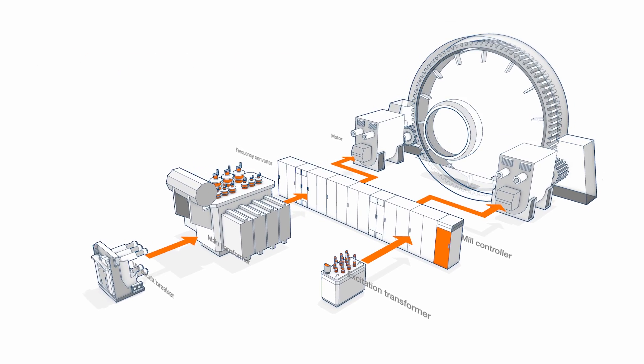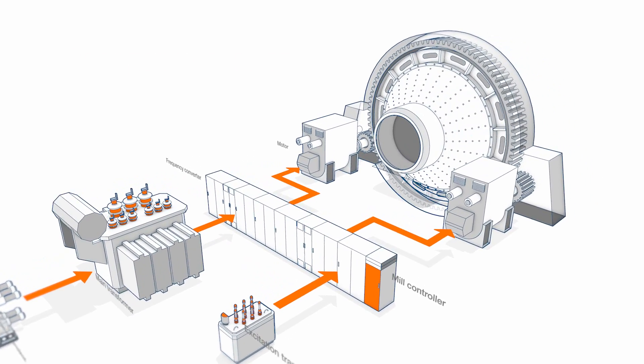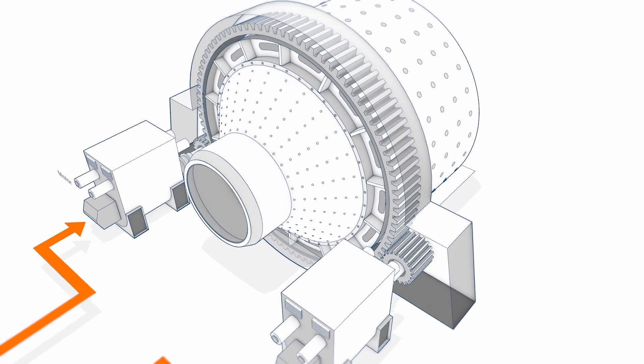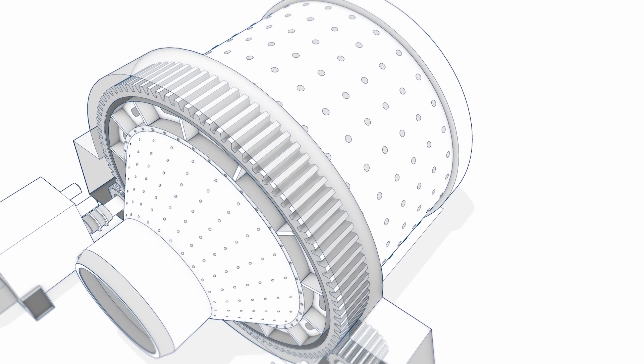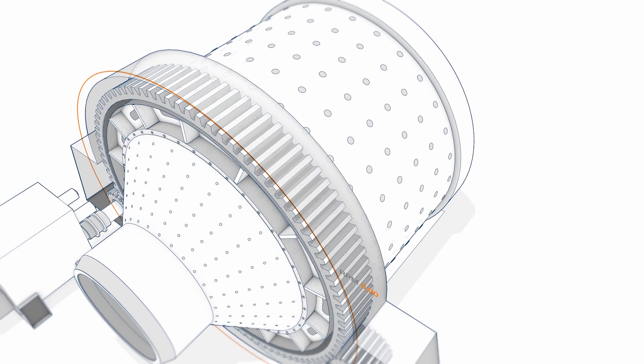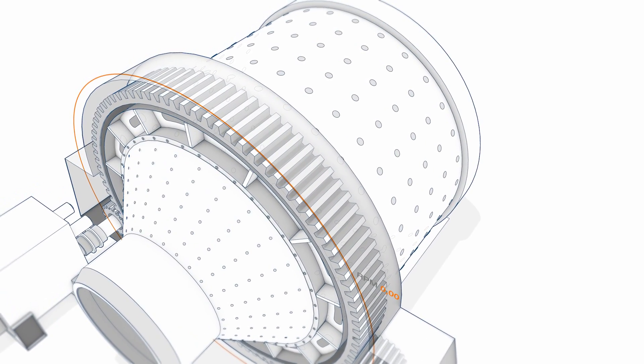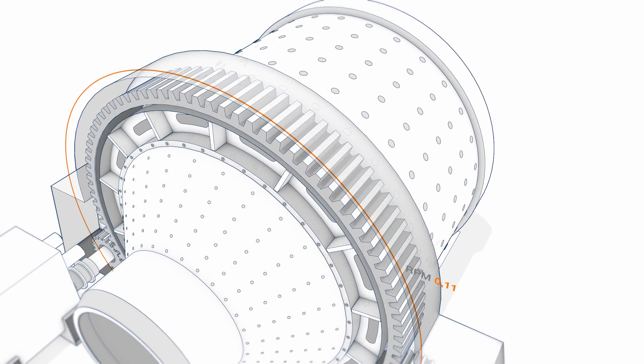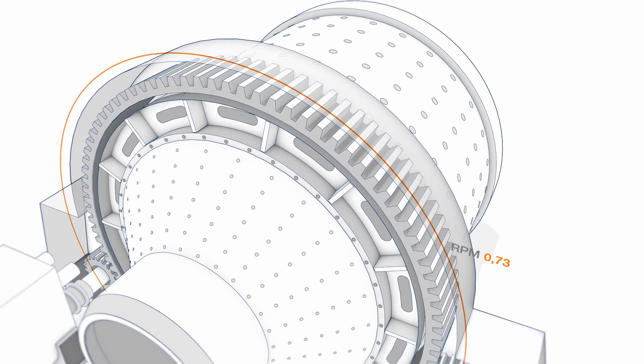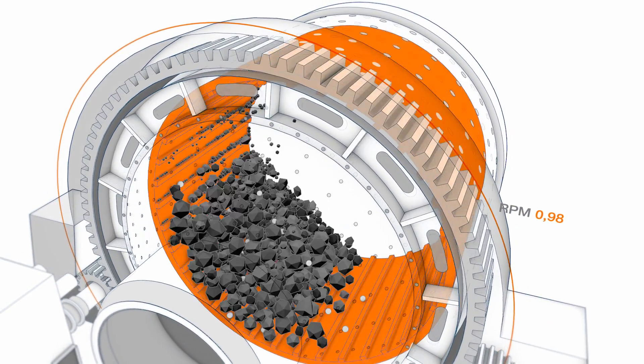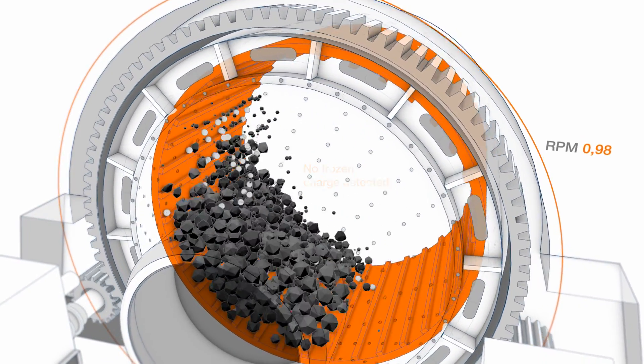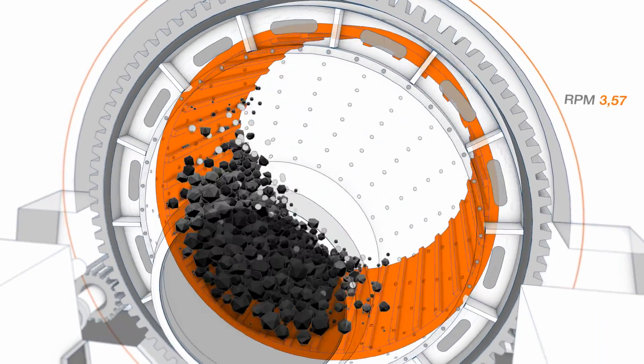Its design allows for smooth and controlled starts with just a simple command from your DCS. The mill starts moving slowly in a frozen charge detection mode. Once the ore input successfully cascades, the drive releases the mill to normal operation and it accelerates to nominal speed.